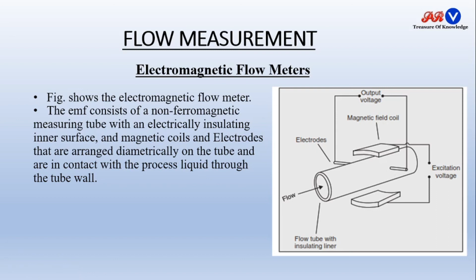Advantage: there is no obstruction to flow that may cause pressure drops, as in earlier cases where we had obstructions caused by the rotor or turbine. Second, the output voltage is linear to the flow rate. Third, the electromagnetic flow meter is manufactured to measure flow in pipes of any size, provided a powerful magnetic field can be produced. If the size of our pipe is large, then we have to apply a large magnetic field. If the size of the pipe is small, then we apply a small magnetic field. The output is unaffected by changes in characteristics of the liquid such as viscosity, pressure and temperature, so it will still give us an accurate reading.